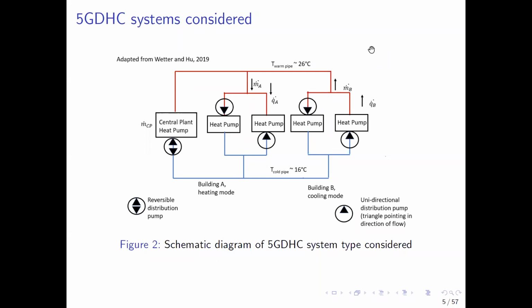5th generation district heating and cooling systems are characterized by the use of distributed water source heat pumps at connected loads, which further temper the water to meet the building's heating and cooling loads. And as shown in this diagram, this system configuration facilitates both bidirectional thermal flow, meaning that each connected load can exchange heat or provide heat rejection from the network, and bidirectional mass flow, in that the dominant direction of mass flow through the loop would be either from the warm pipe to the cool pipe or vice versa, depending on whether heating or cooling loads are dominant in the system.